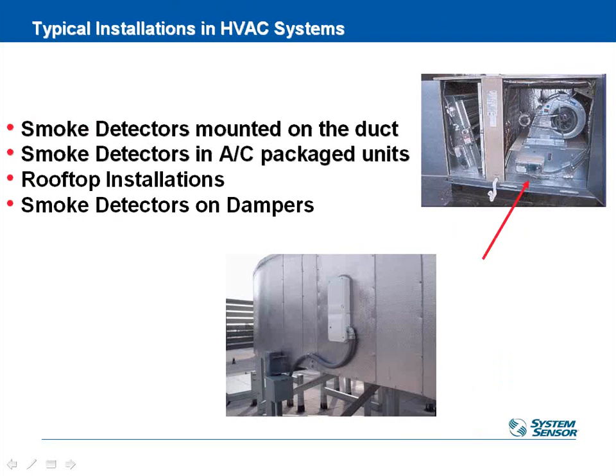Typically, you're going to put them inside the building in the supply or return duct, depending on the code you're following. Typically, you want 6 duct diameters of straight duct upstream and downstream of the detector to ensure that you have good laminar flow. If you don't have good flow, you might have dead pockets, and the air may not actually be hitting the detector, which means any smoke in the system would not be hitting the detector. There's some loopholes around that, but we'll talk about that.